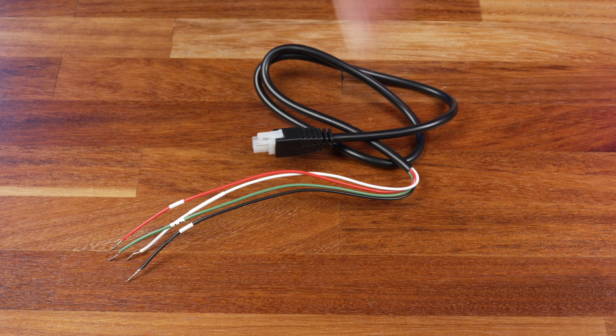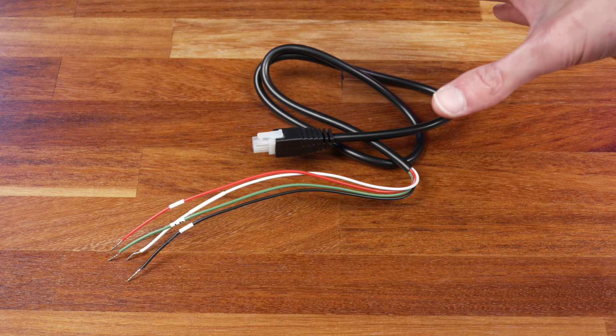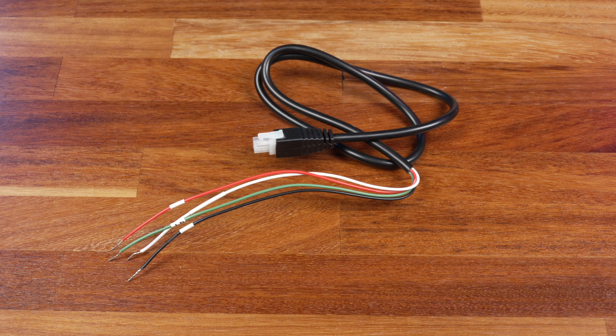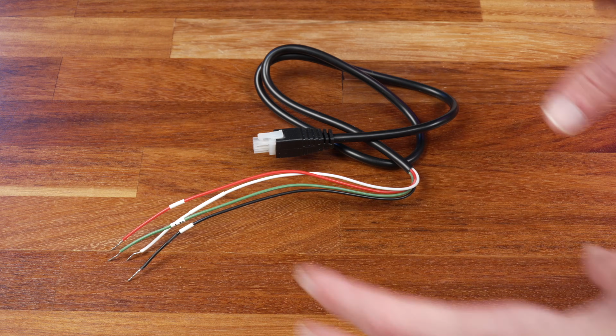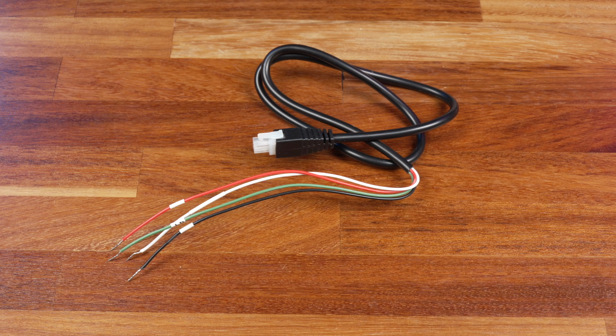Then next up, we have this cable that's used to connect the energy monitor to the electricity supply. Now, you may be wondering why this needs a mains connection rather than just some sort of DC power supply, and that's so that it can monitor the mains voltage to allow it to calculate the power value. If you see an energy monitor like this and all it takes is a DC input, then all you'll be able to do with it is measure the current, not the power, since you don't have any sort of voltage reference.